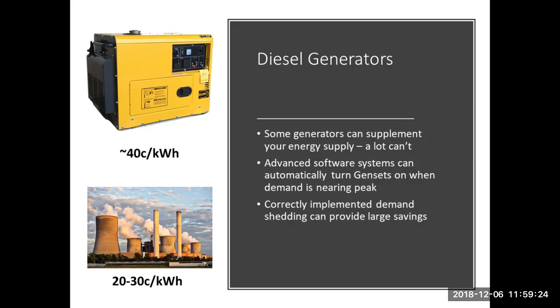One of the other things to keep in mind is that the cost to run a generator is actually quite high. At the moment, diesel was about $1.60 when I put this slide deck together, so it was costing about 40 cents per kilowatt hour. That obviously varies with the cost of diesel, but when you're comparing it to grid electricity, which is on average around 20 to 30 cents per kilowatt hour, it is a bit more expensive. So it's only really useful if you are effectively managing your demand, but a lot of them aren't set up to do that.